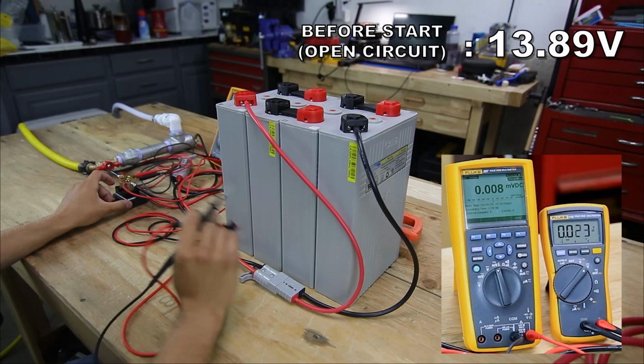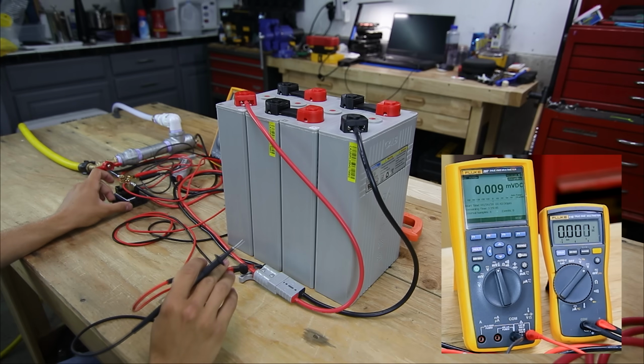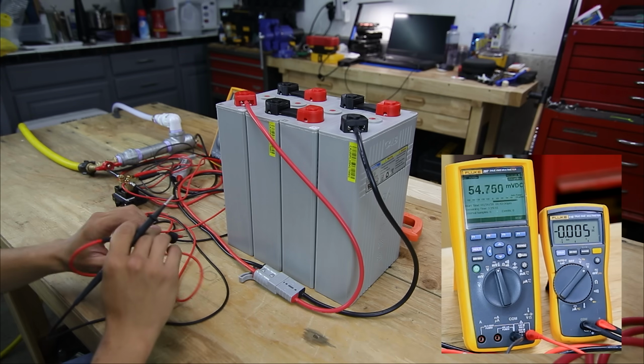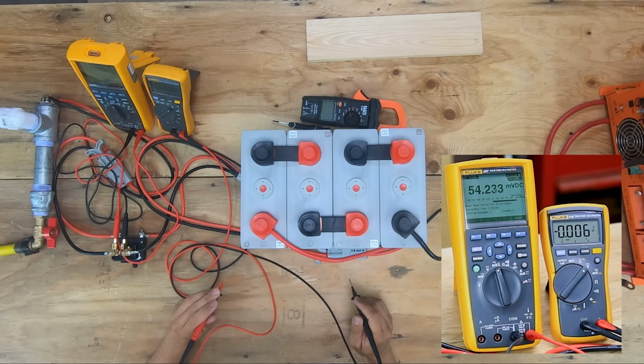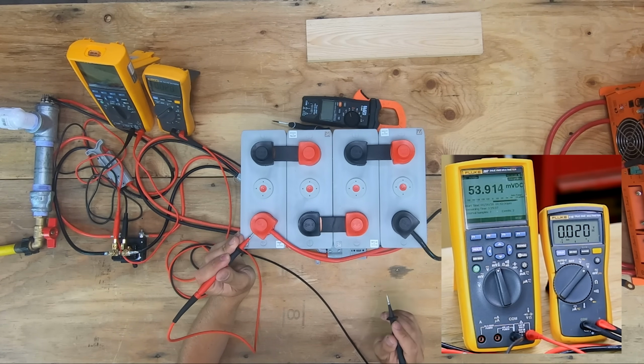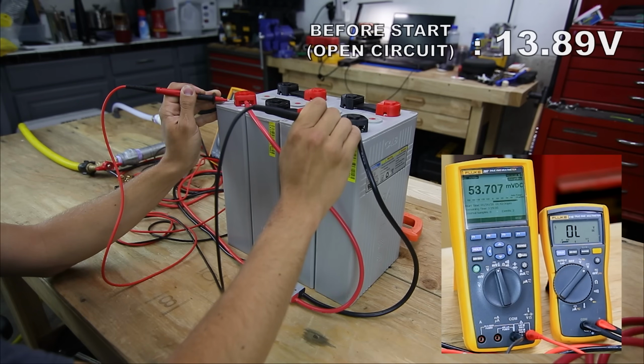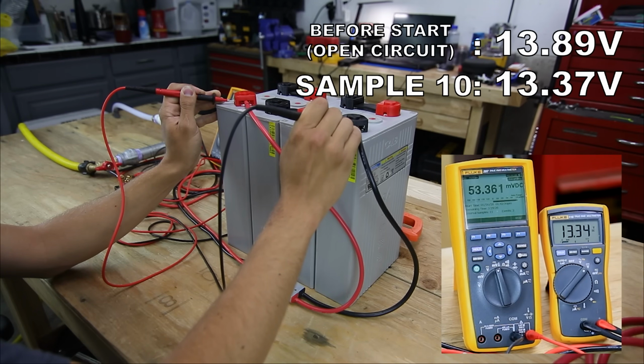I'm going to start the test, and the meter is already recording. I'm going to start at the beginning of sample 6, which is now. I immediately had 54.7 amps, and it's starting to drop. My battery voltage at sample 10 is 13.37 volts.